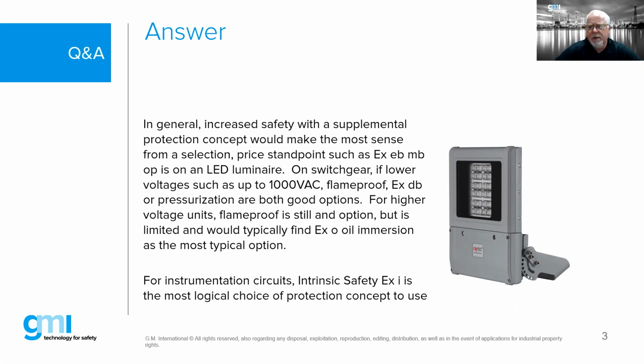IS would make the most sense for most applications involving low voltage or instrumentation circuits. You cannot use energy limitation when the energy that you need to use is 1,000 volts.